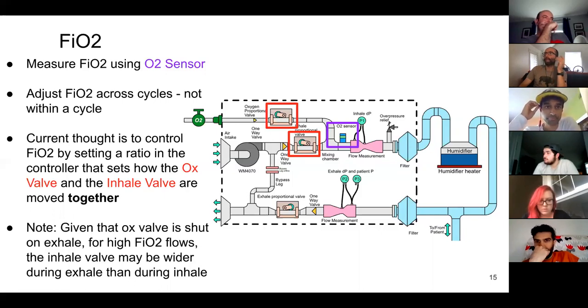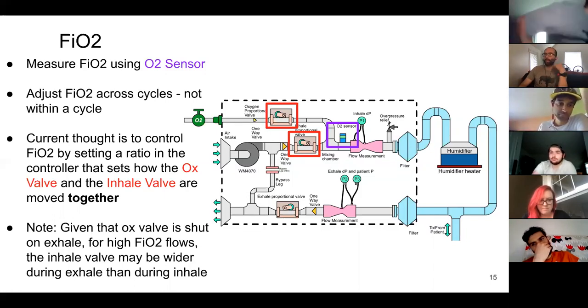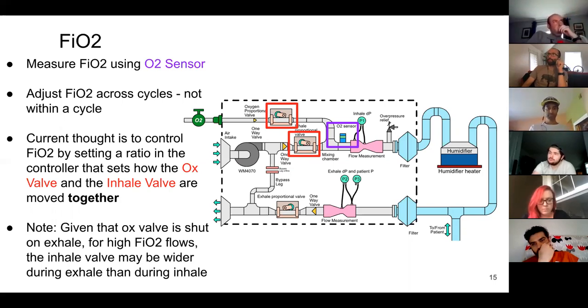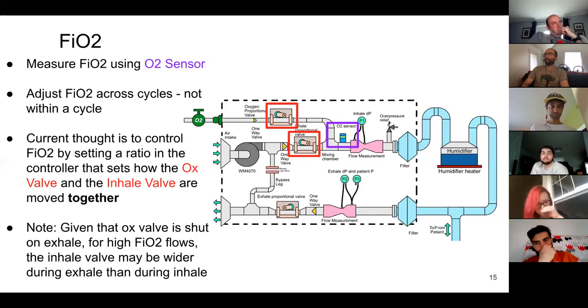The reason we're pursuing pressure-based control is we have lingering issues with flow measurement, and we're not doing a fixed volume method. So we have to essentially sense flow to get volume, and we're less confident in that than our ability to sense pressure. So we are targeting pressure control modes with and without volume-based adaptation, with the impression that we just have better control of pressure than volume. Hopefully, as we get some of the sensor issues worked out and narrow down on a control strategy there, we'll be able to implement a volume-based mode in software with the same architecture. It's better, especially while we're working early in the system, to have the control strategy closed around the pressure that we're measuring directly rather than the twice integrated volume measurement.